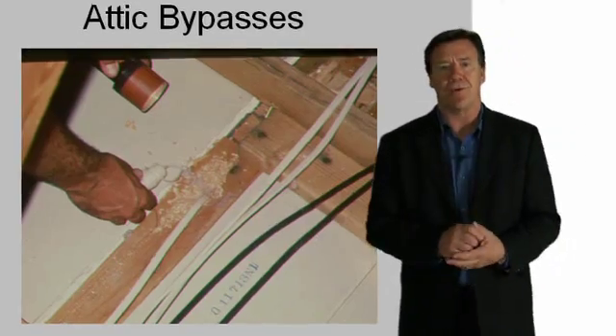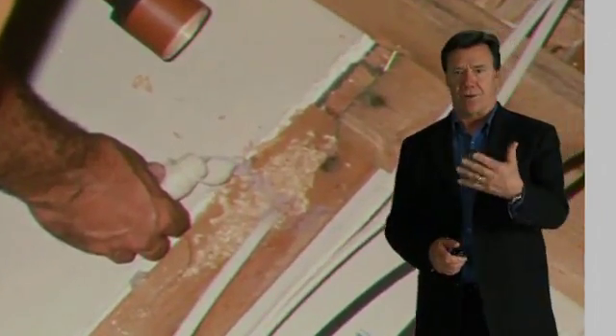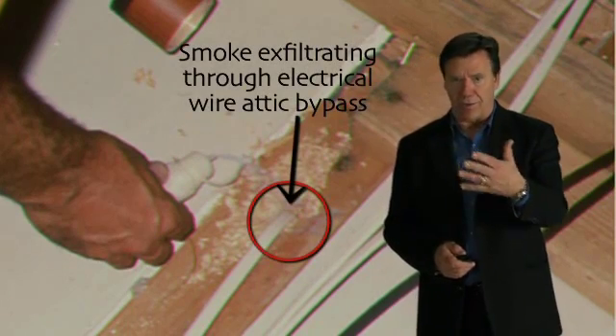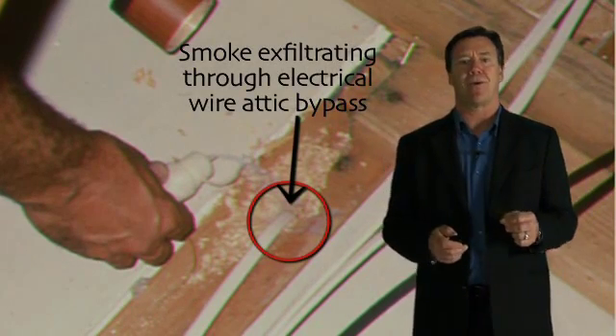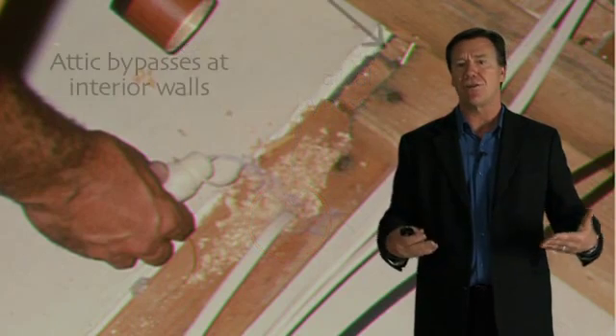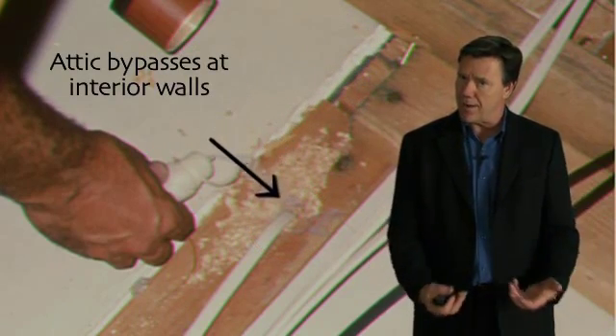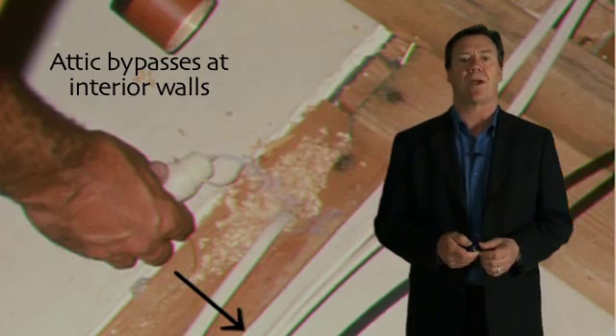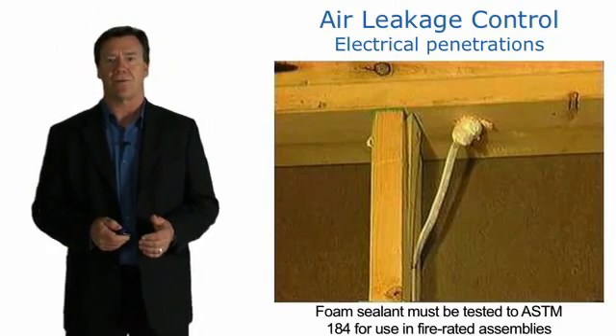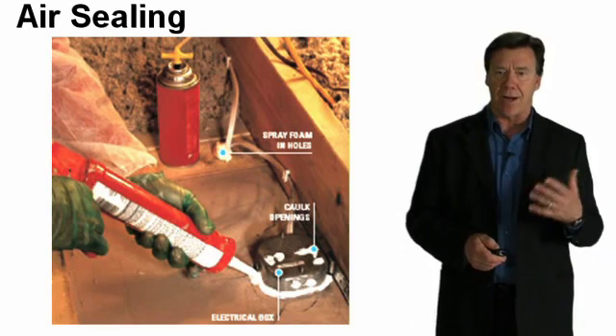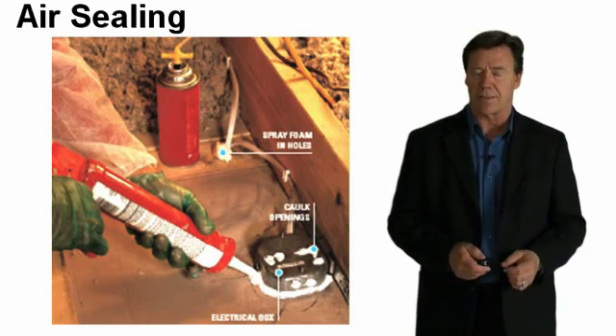Here you can see an attic bypass — a significant amount of air can infiltrate or exfiltrate not only where wiring is located, but also up in attics where interior walls have drywall. We definitely want to seal all these penetrations, and that can be done a variety of ways. Spray foam is one option; caulks and sealants are another. We want to make sure they're resilient enough to expand and contract with the building envelope.